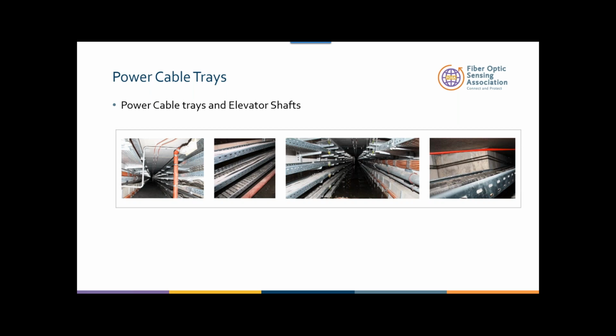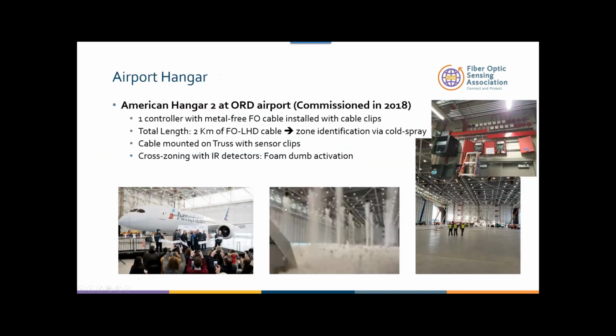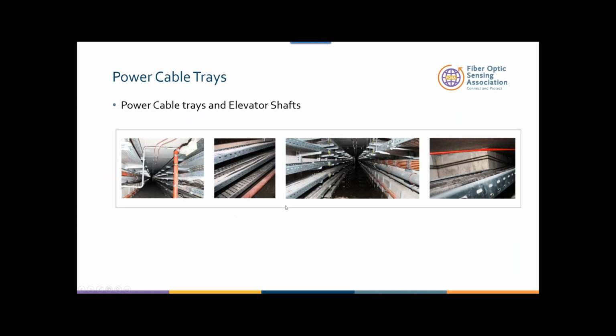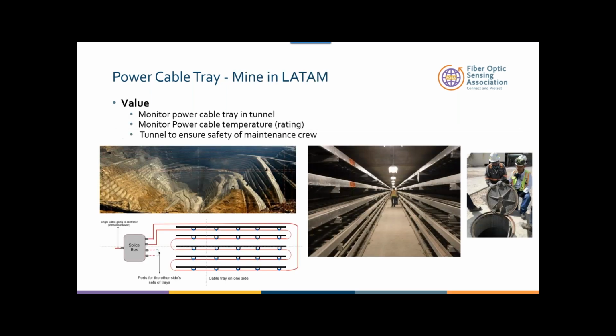But you can also go to an elevator shaft and then be able to monitor the temperature as well. So from a sensing point of view, you can stop a fire and you can activate an alarm before it's too late. An example of a fiber optic cable tray approach: here on the left is a mine in Latin America, for instance, where you have a splice box. And this cable tray is in a tunnel. The ability to monitor each one of those rows is very important.